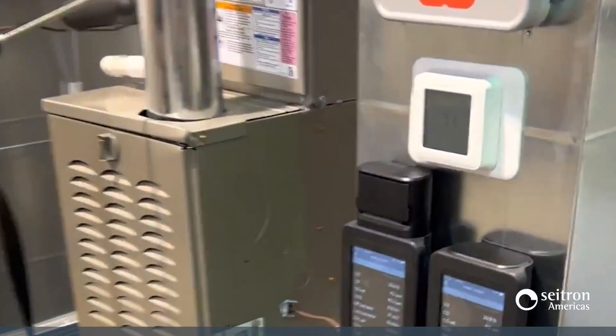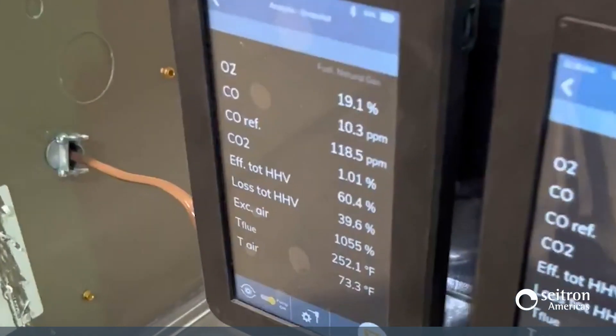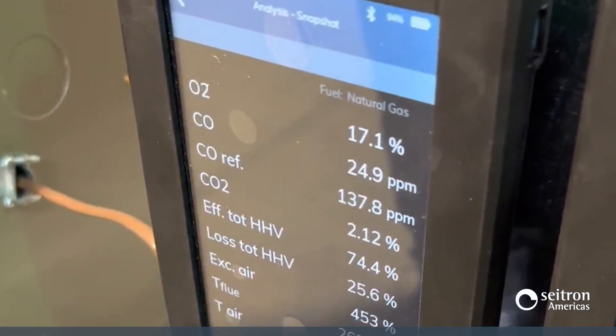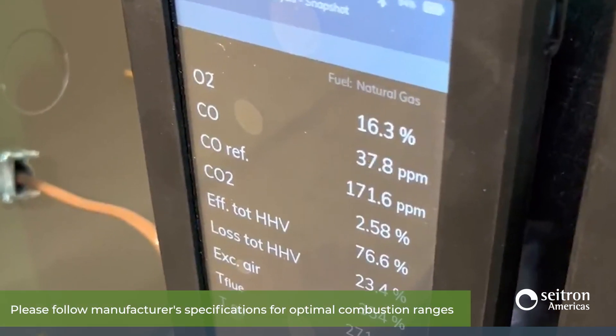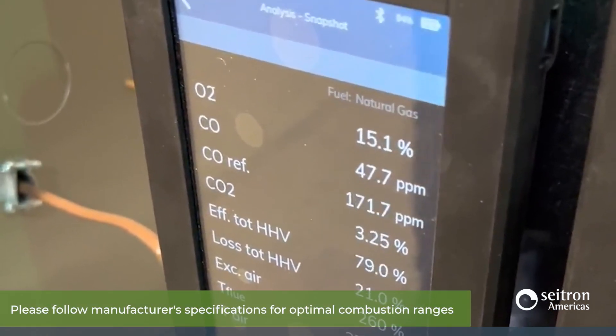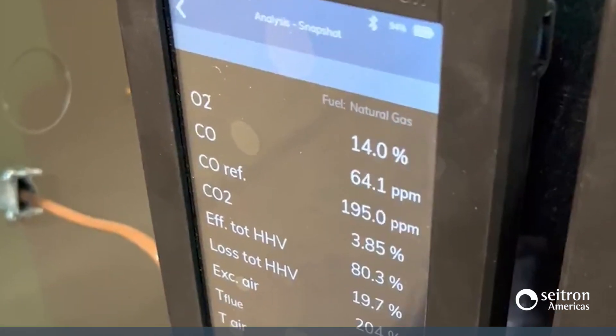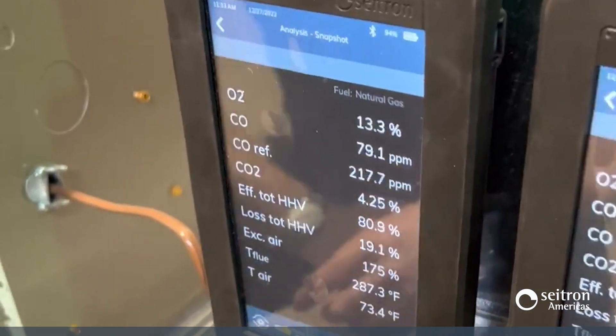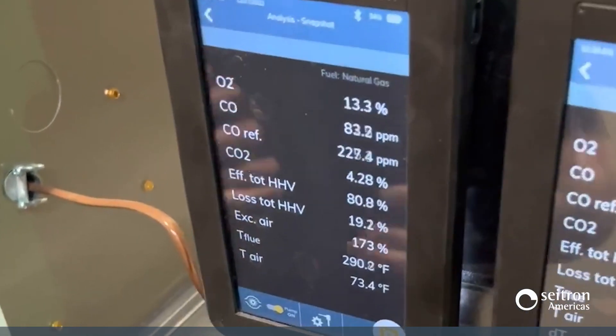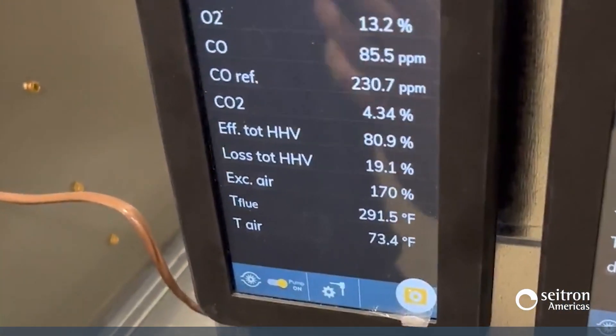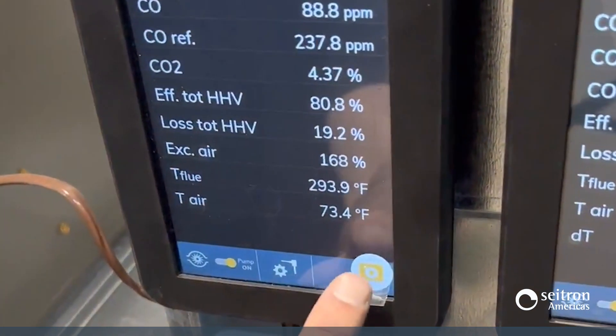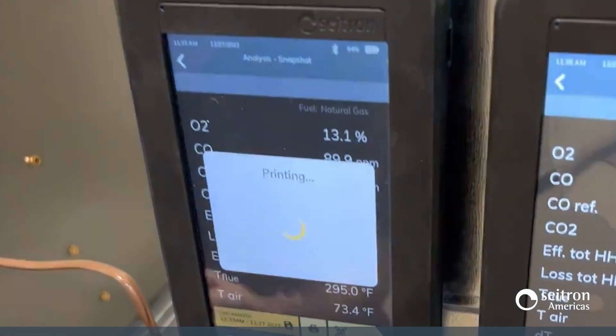Now we can see that our flue gas measurements are beginning to change. Oxygen is dropping down, carbon monoxide and carbon monoxide air-free are beginning to increase, as well as our CO2. We also see our combustion efficiency hovering around 80% efficiency. If I want to save my combustion results once they are within the range from the cheat sheet, I'll hit the snapshot button to freeze my readings, and then I can print out directly to the built-in printer on the Novo Analyzer.